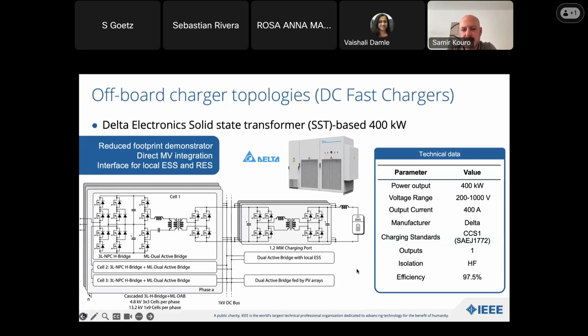This one is intended for megawatt charging systems in the long run — the ones Sebastian talked about working at higher power levels — in which you can integrate energy storage systems to reduce consumption from the grid during peak charging periods when you're demanding a lot of power from the grid. Then you can use it from this local battery array and reduce stress on the grid.